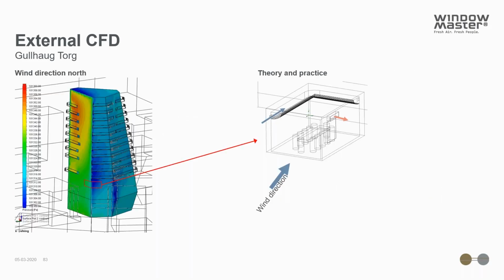We can look at specific areas of the building and calculate how much the attached operable windows need to open to achieve a certain ventilation rate. As an example, we can look at this corner room of the building and figure out how much the windows should open specifically in this room based on the surroundings, floor levels, and orientation.